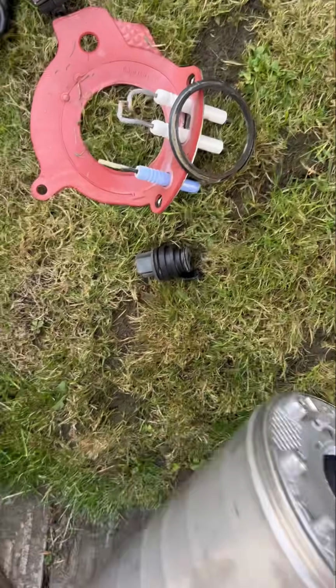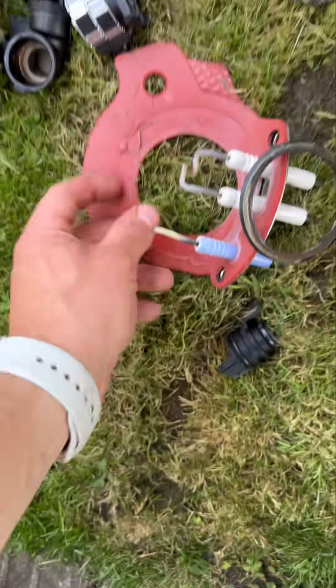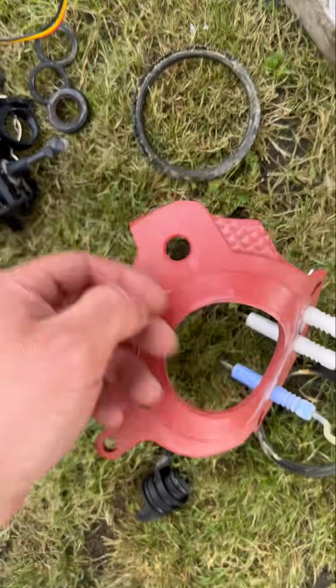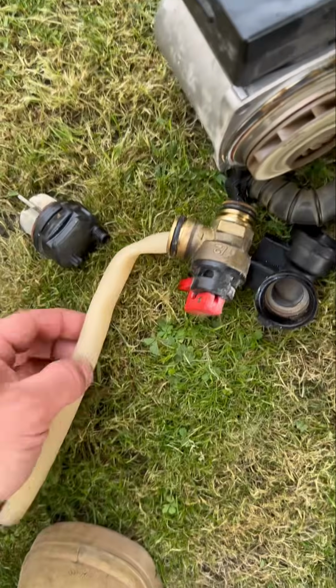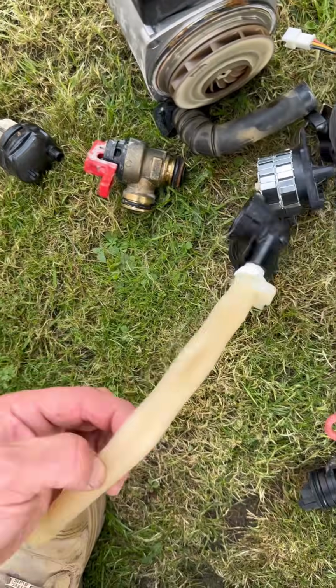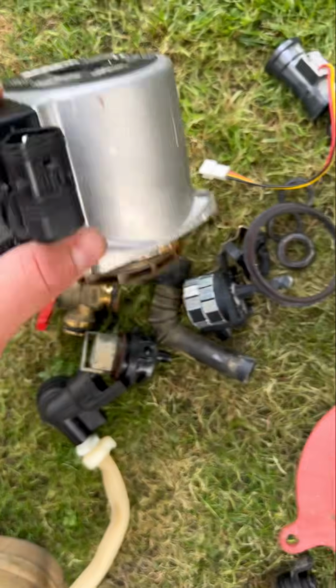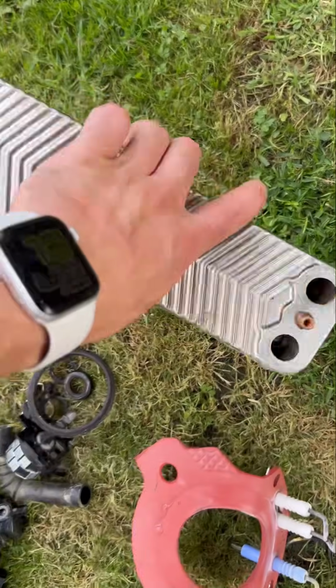See that heat exchanger split there? We've got the flow adapter, electrodes, diverter valve motor, washers, sensor, flow elbow, PRV, auto air vent, pump, if I haven't already said pump. Basically rebuilt the boiler, to be fair, on a new plate.